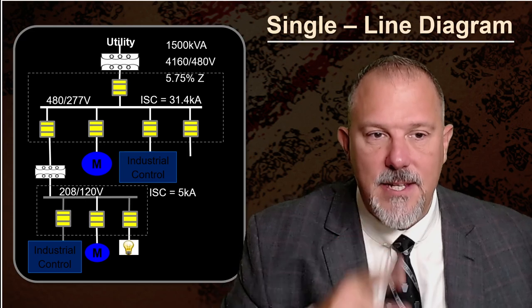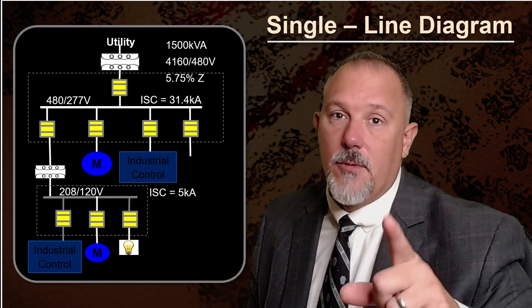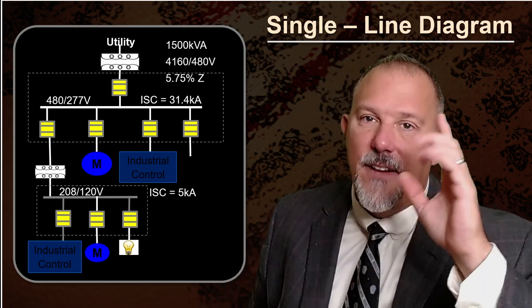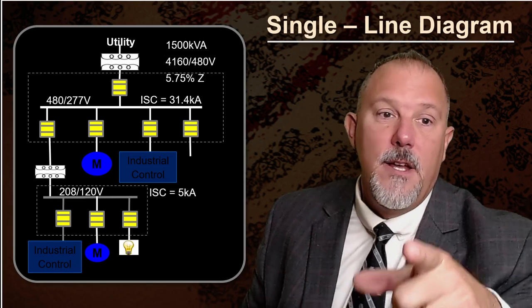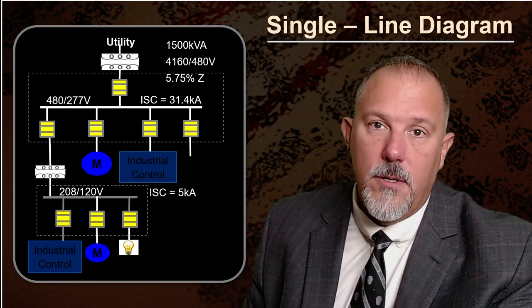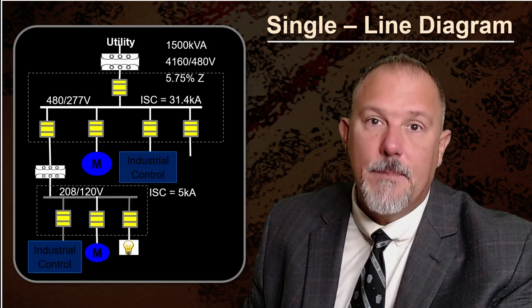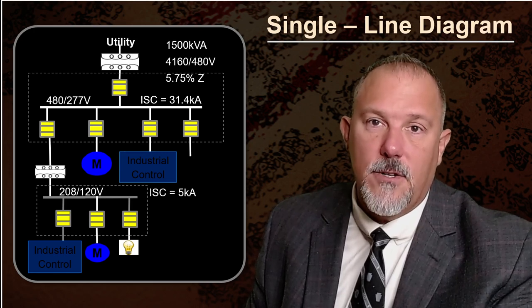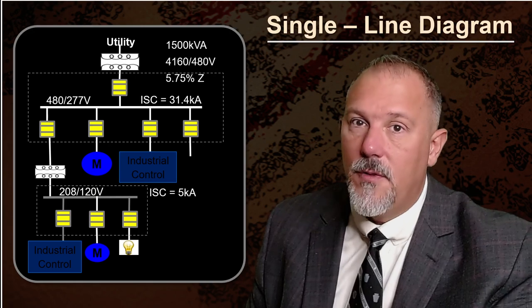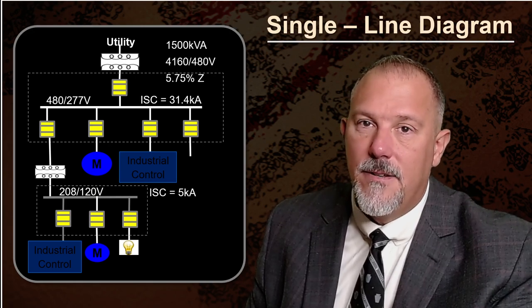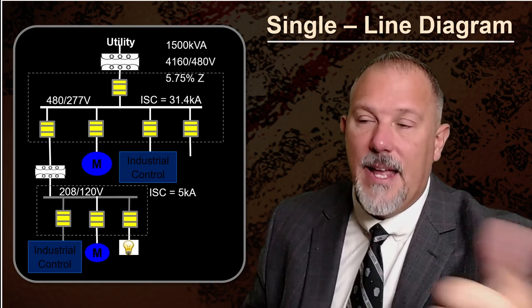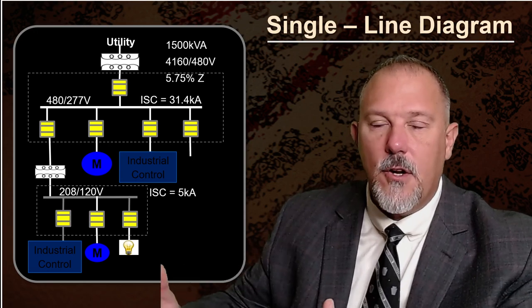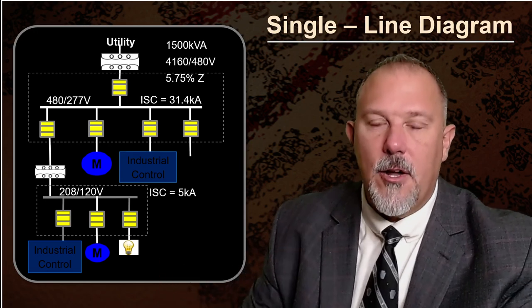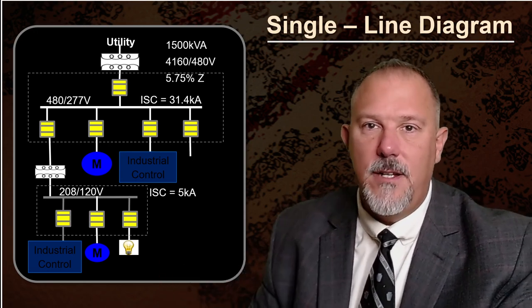The energy on the secondary of that transformer is not going to be reduced because I have a very large overcurrent device. The panel board that is fed from a tap conductor: the overcurrent protective device is larger than the conductor size. Think about it. I have inflated my overcurrent protective device. The chances of my arcing current being in the instantaneous region are very low.